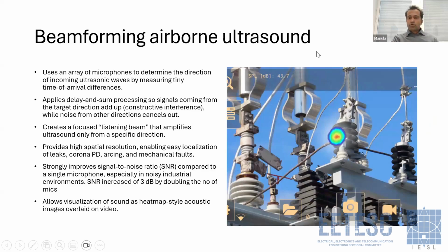So this is the output of the ultrasound camera. It gets the sound source location from the beamforming, and it overlays it on the optical camera view. When these cameras are produced, this alignment is done with a known sound source. Once this alignment is done, it can be used anywhere in the world to detect whatever ultrasound source. In this example, it is located at a partial discharge on this insulator, and this so-called heat map is overlaid on the optical camera view. So users can quickly scan whatever area they want and locate the ultrasound sources.